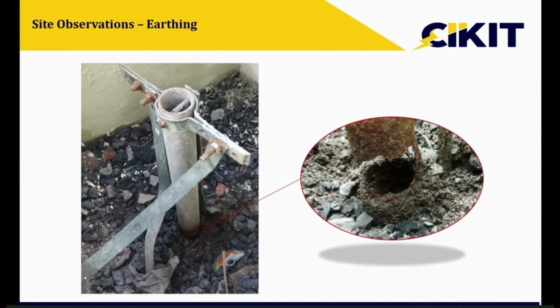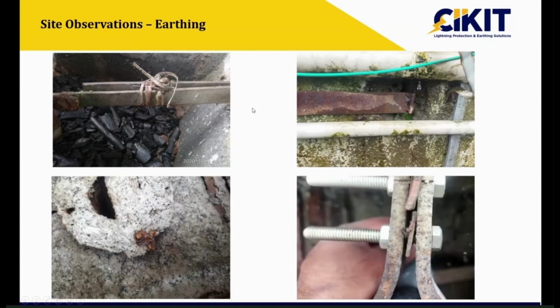If you want to check the actual condition of the conductor, we have to remove the top layer of the soil and check the condition at this point. So these are different observations. In the first image, the connection is not proper. In the second one, it is corroded. In the third one, that is concrete waste.